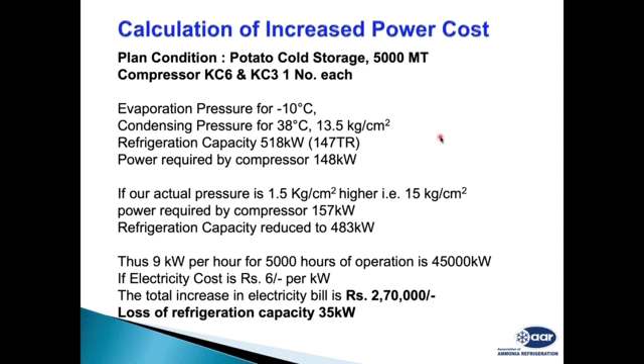Typically, a very regular application in India is potato cold storage. We have more than 14,000 potato cold storages in India. Typically, 5,000 metric tons is a very standard cold storage. So I have made this case study for this. These are practical results obtained from a potato cold storage, where we have one 6-cylinder and one 3-cylinder compressor running continuously at -10 degree evaporating and 38 degree condensing.